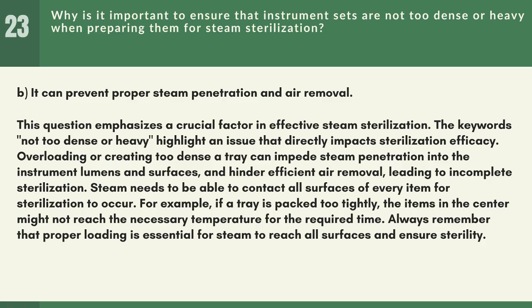Steam needs to be able to contact all surfaces of every item for sterilization to occur. For example, if a tray is packed too tightly, the items in the center might not reach the necessary temperature for the required time. Always remember that proper loading is essential for steam to reach all surfaces and ensure sterility.